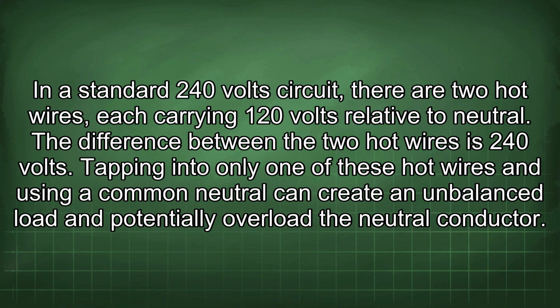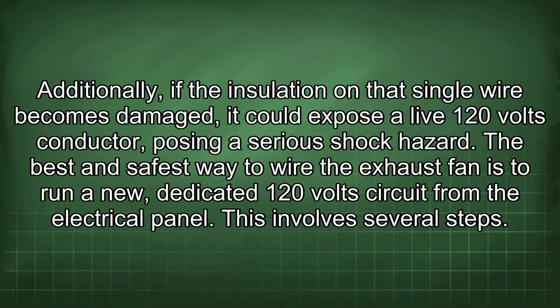Using a single wire from a 240-volt circuit to derive 120 volts introduces a significant safety risk. In a standard 240-volt circuit, there are two hot wires, each carrying 120 volts relative to neutral. The difference between the two hot wires is 240 volts. Tapping into only one of these hot wires and using a common neutral can create an unbalanced load and potentially overload the neutral conductor. Additionally, if the insulation on that single wire becomes damaged, it could expose a live 120 volts conductor, posing a serious shock hazard.